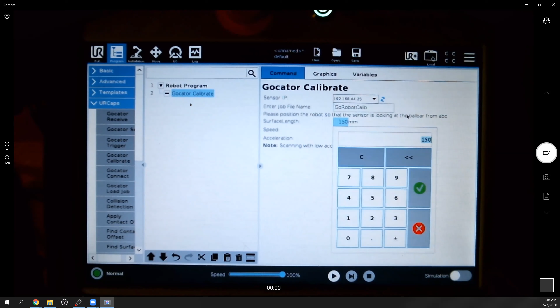A little bit faster with my finger. Again, this is where I was saying you can pick whatever surface length that you need. So for my ball bar calibrator, it's only about 40 millimeters, 150 is fine. Again, this is for if you have a sensor that's larger or smaller than the 2330, and of course the calibrator size.